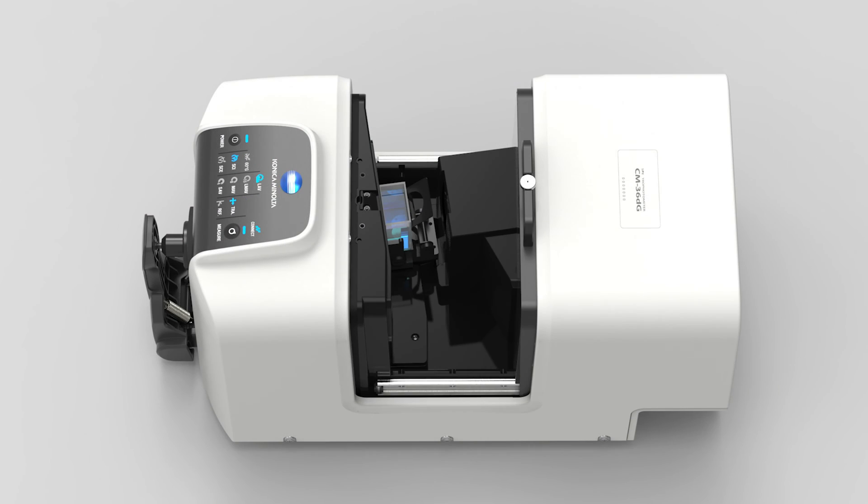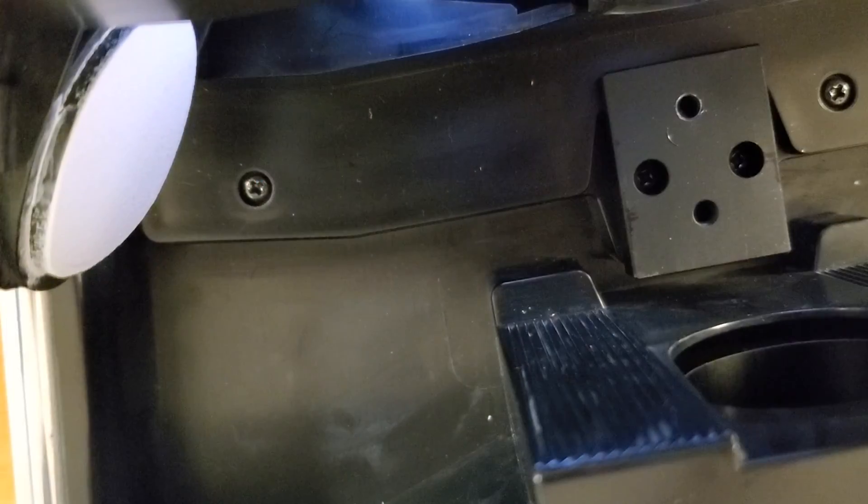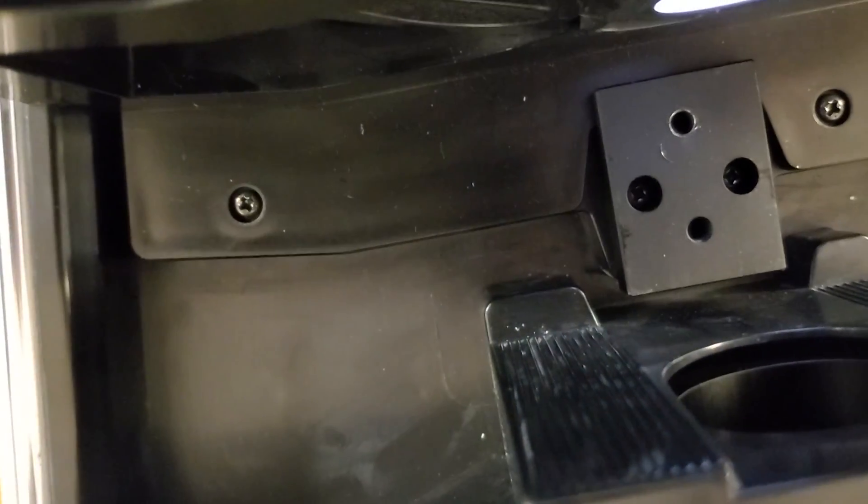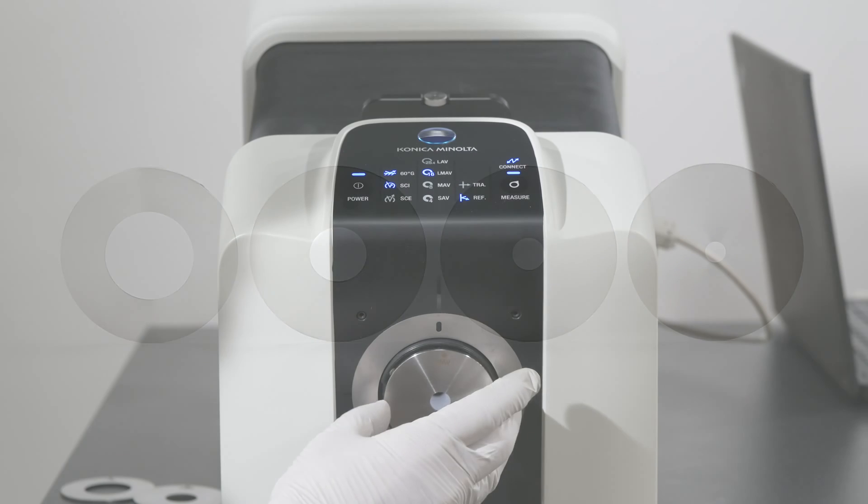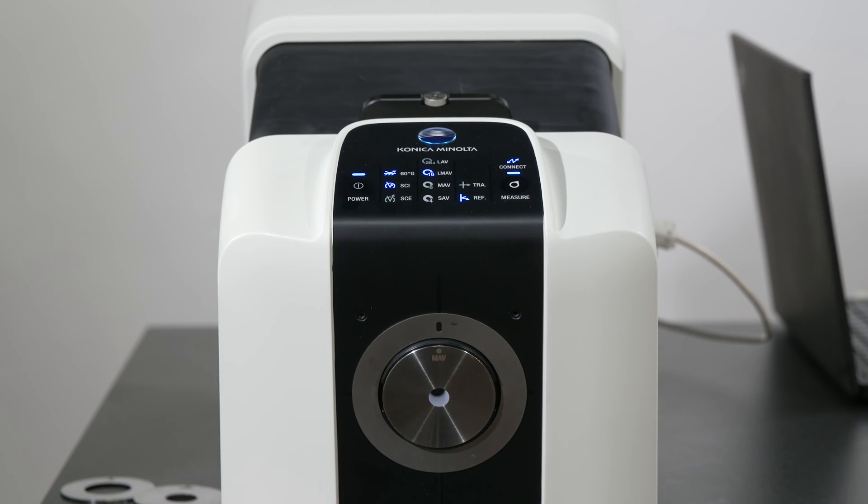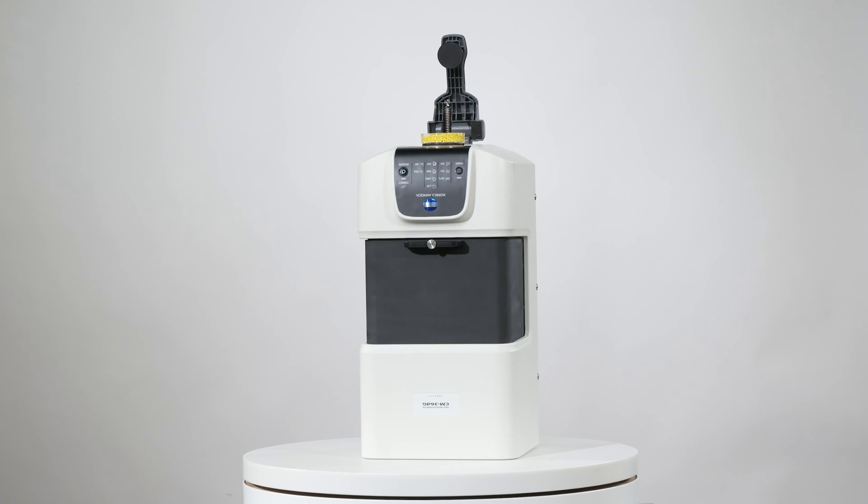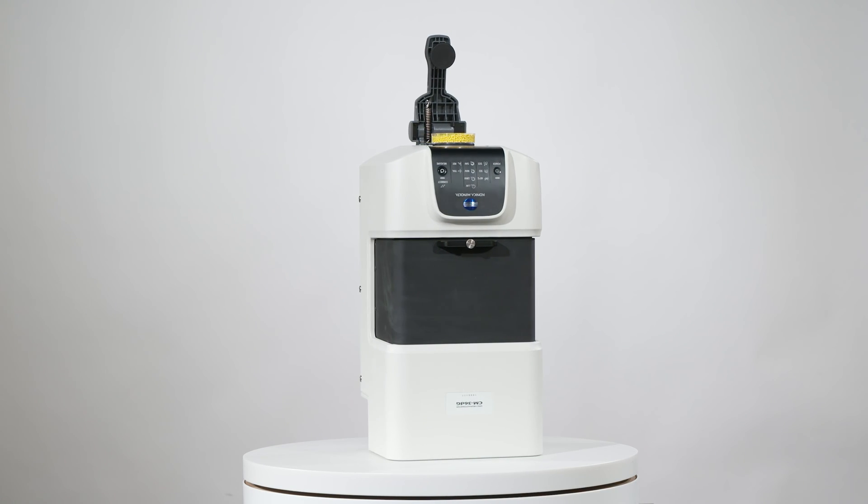The CM-36dG includes several new features to improve the user experience: a larger transmission chamber, SCI-SCE mechanical port, an integrated camera viewfinder for video preview of the sample, four target masks, auto detection of target masks shown on the display indicator, and the instrument can be placed vertically for top loading measurements.